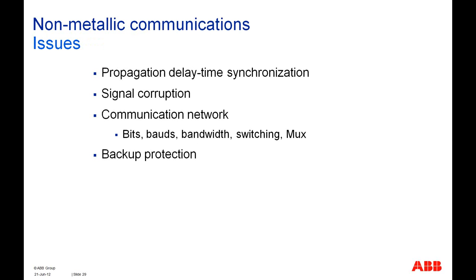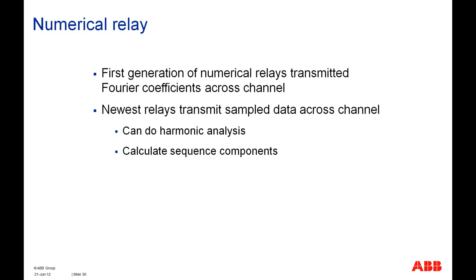So one was the situation that okay, we have gone away from the metallic communication. Non-metallic communication, like wireless, also has some disadvantages, which are, for example, signal corruption, propagation delay, and time synchronization. These are the problems for the non-metallic communication. So the basic idea was to use non-metallic communication, but with fiber optics. Right now, most of the line differential protections employ either direct fiber optic or communication through telecommunication networks.